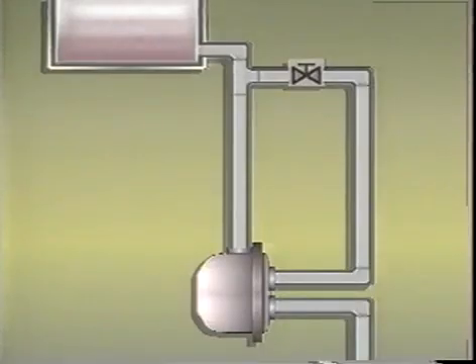To avoid differential shock arising from this situation, use an F&T trap and back vent it to the top of the vertical line to maintain near equal pressure throughout the riser, even if a slug of condensate forms.